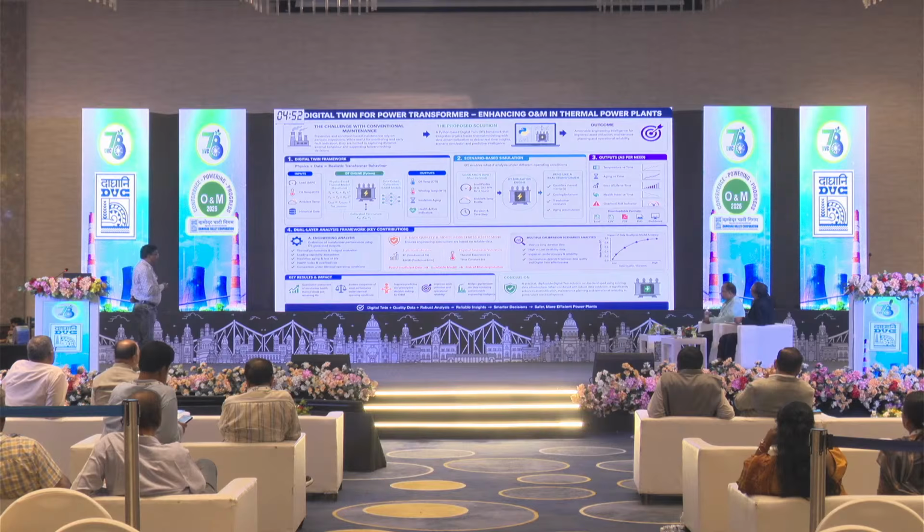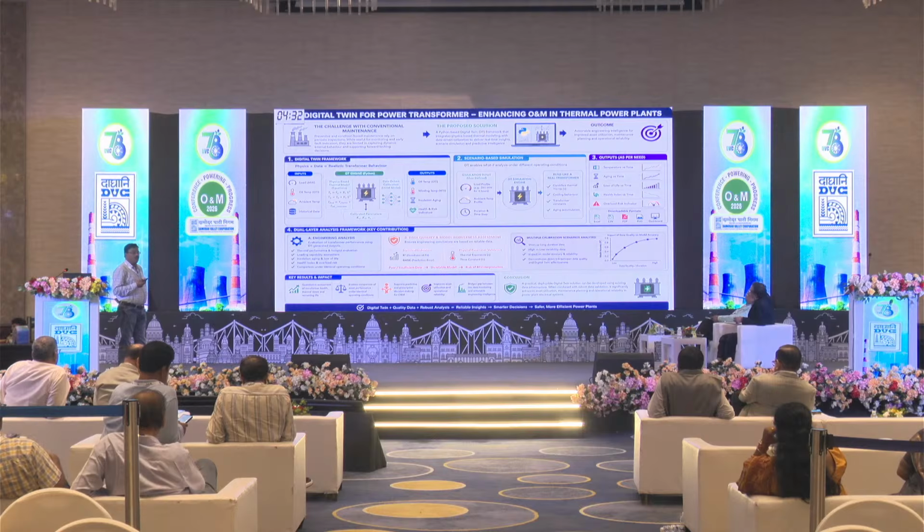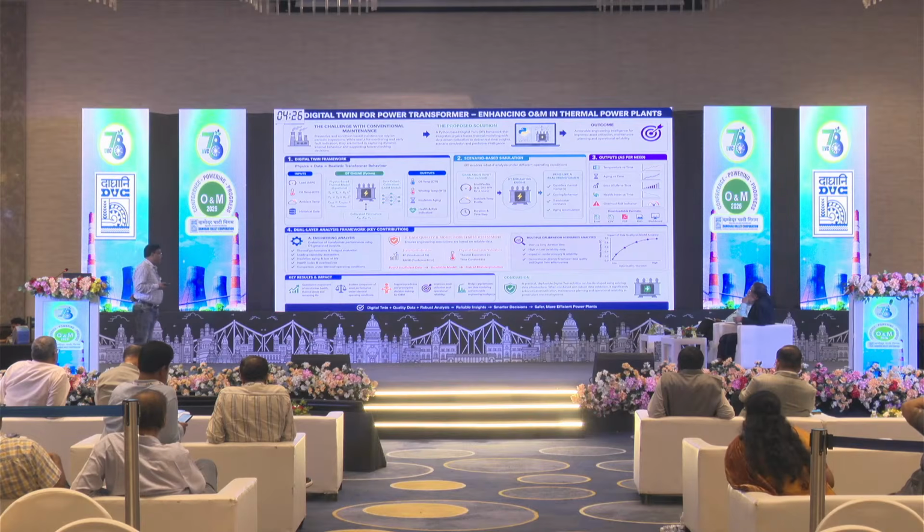Here you can take R square. R square value should be 1. But I am sharing my experience while calibrating my model. I got an R square value of 0.1. What does it mean? The rest of the parameters are well within limit, but this R square is 0.1. Actually, I had trained my model on a transformer of 325 MVA rating from a loading of 250 megawatt to 310 megawatt.